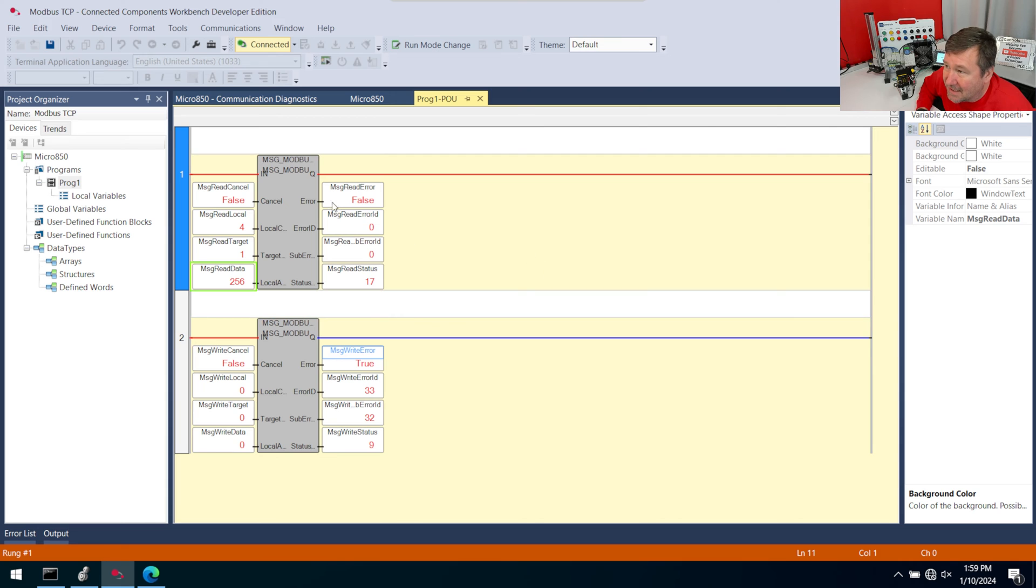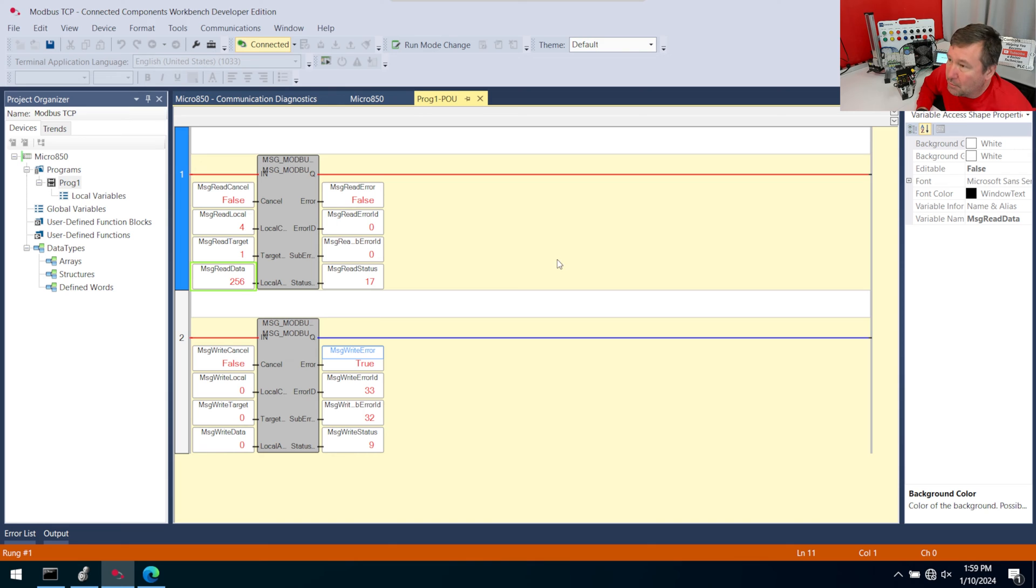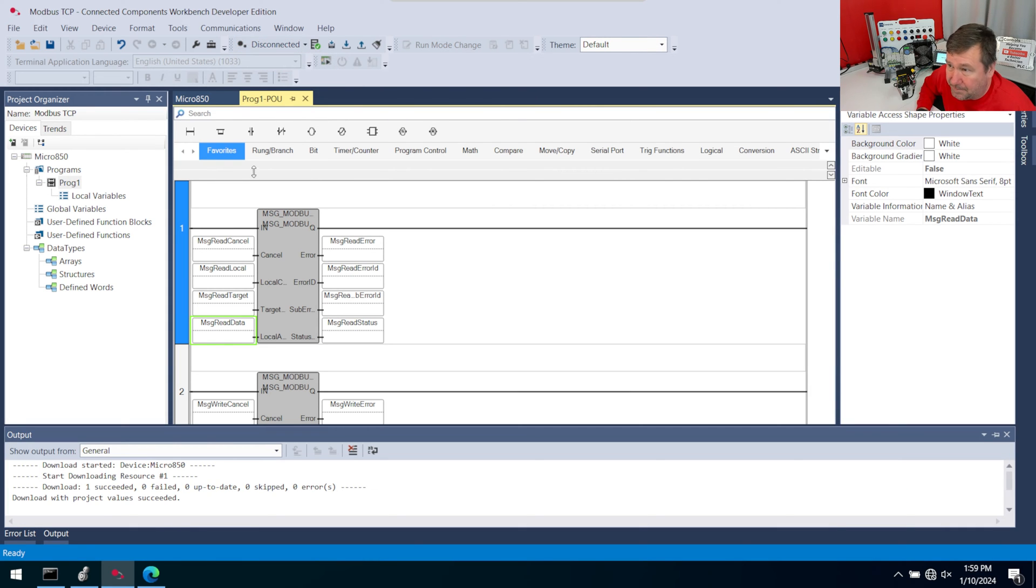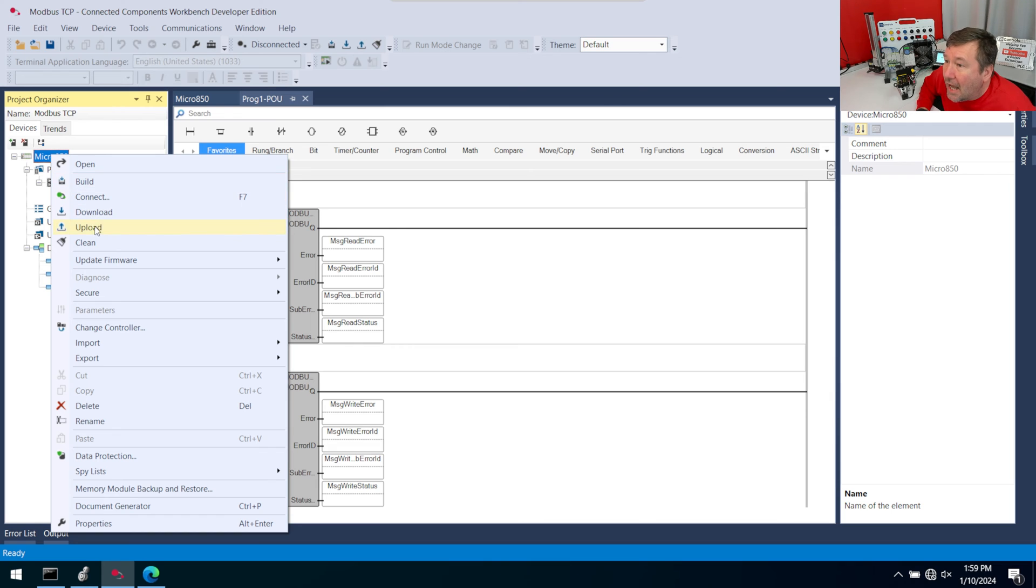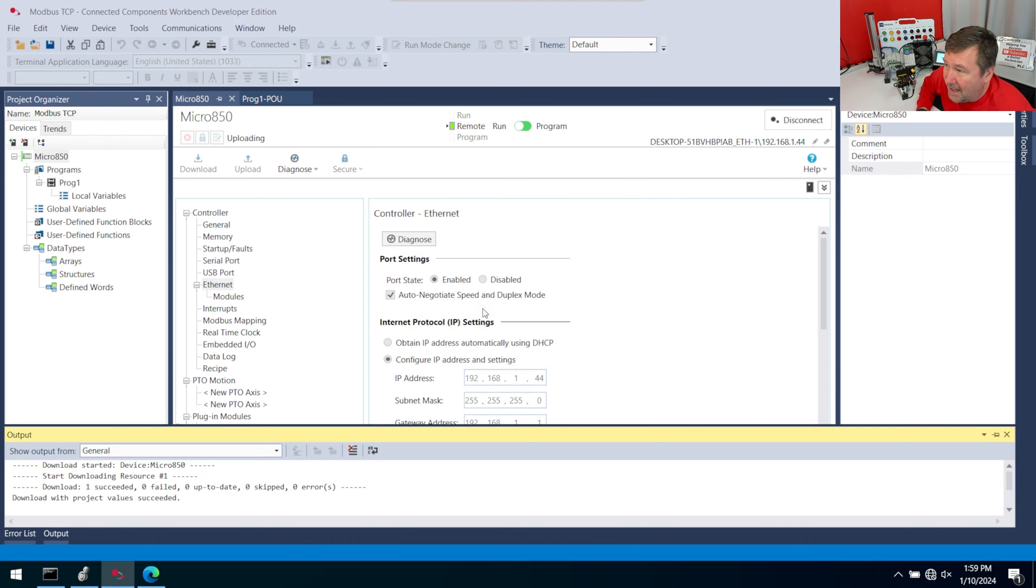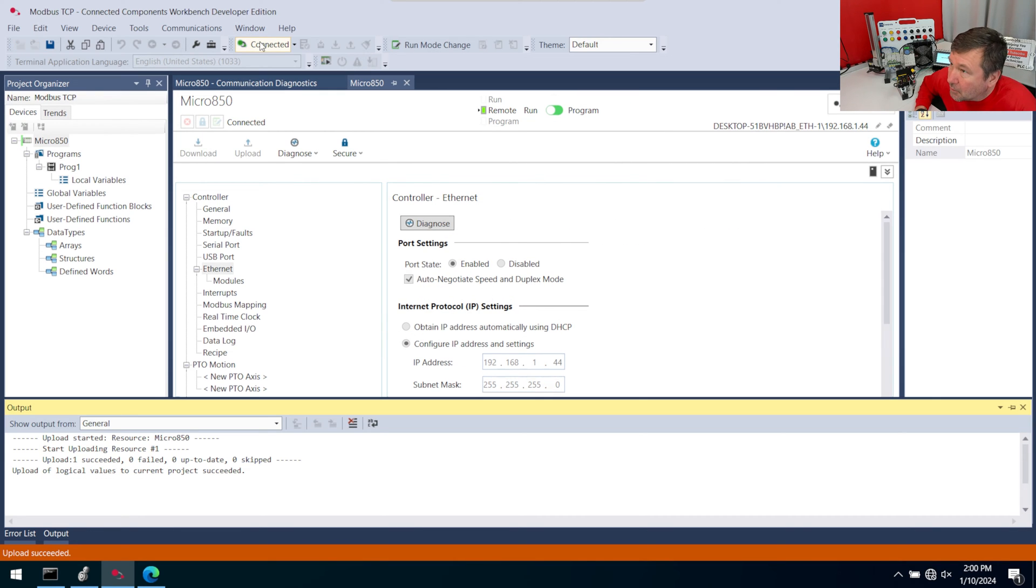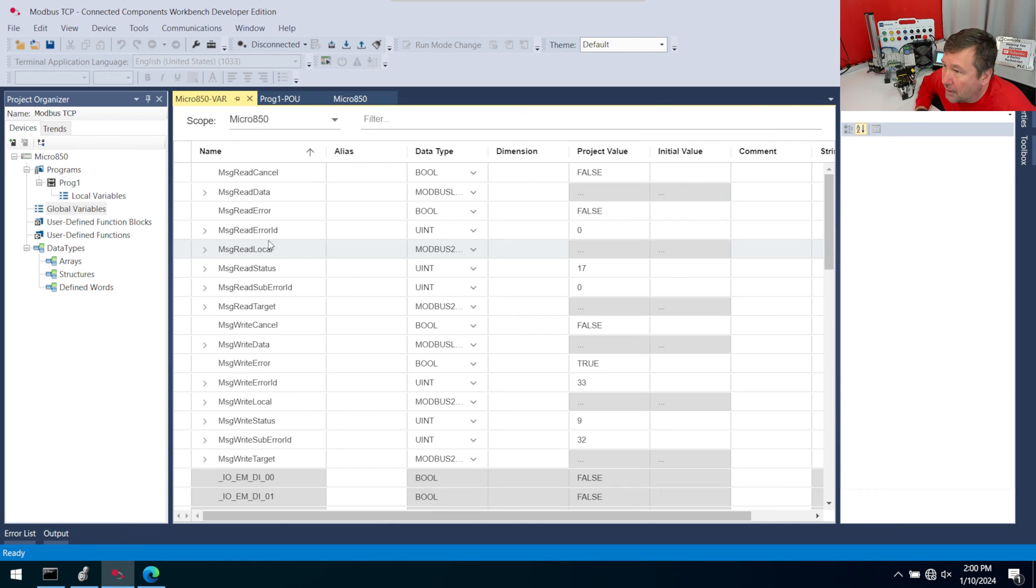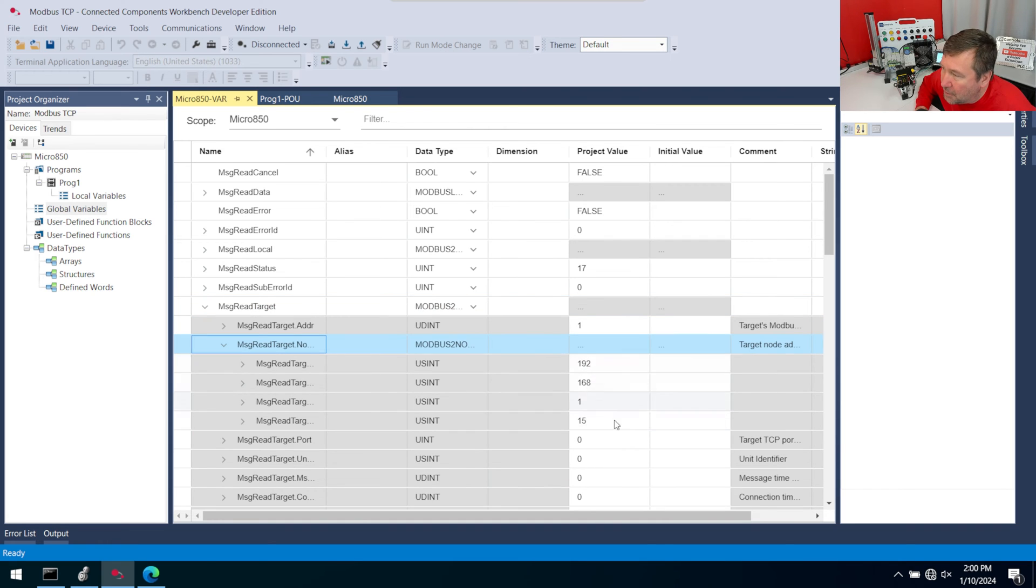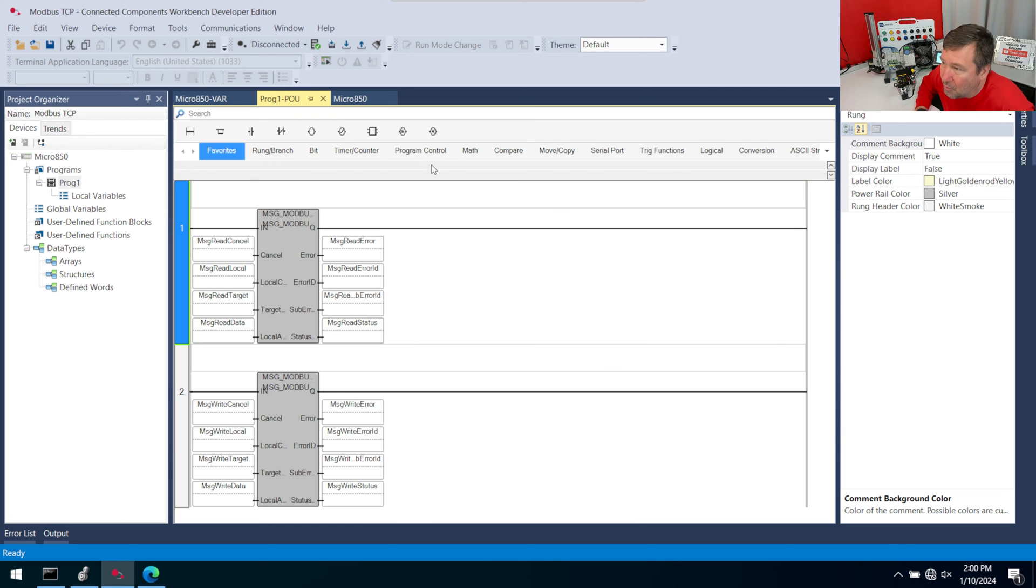One big difference between Studio 5000 and Connected Components Workbench is if I hit the Save button in Studio 5000, I get a prompt here that asks me if I want to upload the data values. You don't get that in Connected Components Workbench. So what we're going to do is we're going to hit the button that says Connected right now that takes us offline. And then we're going to right-click the Micro 850 and we're going to upload. This is going to upload the exact program that we just made, but we have uploaded with logical values here. And then we're going to disconnect again. And then let's double-click on our global variables and get the message read target data. And when we open it up, notice we have our data now. If you did not do that step, when you go to download what we're getting ready to do, you're going to have to fill all these in again.